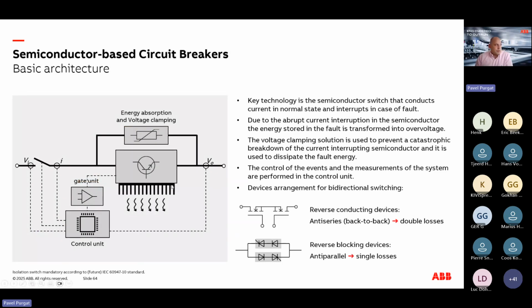A solid-state circuit breaker consists of, let's say, 3 main parts. First, of course, are the semiconductor switches that are conducting the current in the normal state and switching it off during the short circuit. Then we need an energy absorption device, because as you can imagine, as the current is growing in the DC grid, there is inductance in that system. And the energy stored in the inductance, or in the magnetic field, is growing as well. And this energy needs to be released somewhere. And that's why voltage clamping is so important. Otherwise, you would have overvoltages in the system each time we interrupt a short circuit current.